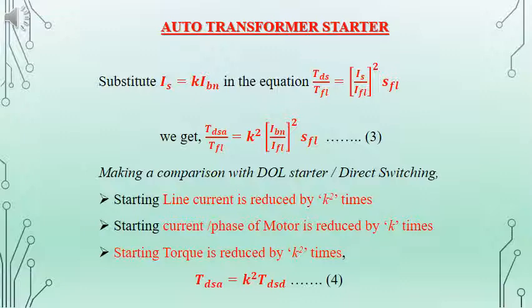Here, by using an auto transformer starter, the starting line current will be reduced by K square times that of the normal starting current, the starting current for the motor will be reduced by K times, and the torque will be reduced by K square times.